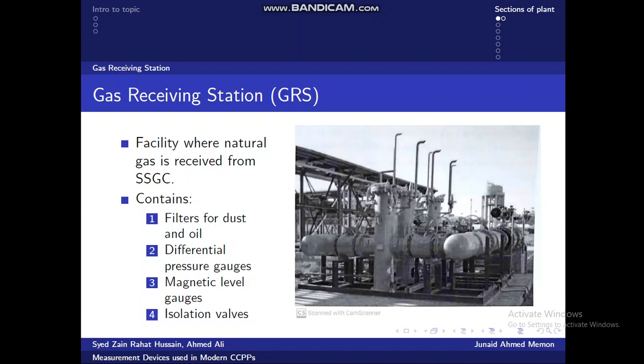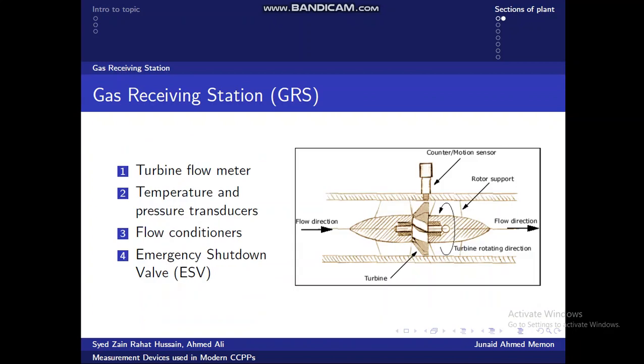So we have differential pressure gauges and transmitters that are installed before and after each filter, where a significant change in the pressure will indicate that the filter has choked or been blocked, and it immediately requires maintenance. We also have a magnetic flow type level gauge that is present to measure the amount of oil. So any oil that may be present would have to be removed for safe operation, and then any filter can be taken out of service by using the inlet and outlet isolation valves.